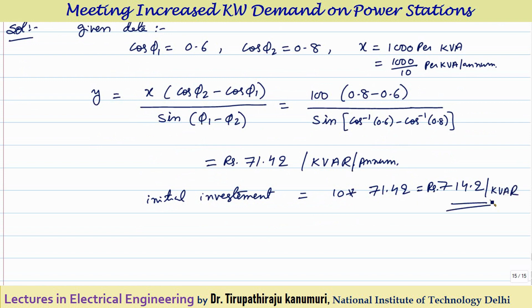So the limiting initial investment is 10 times this, giving 714.2 Rs per kVAR. Up to this cost of power factor improvement equipment, it is economical to go for power factor improvement. If the cost of your power factor improvement equipment is greater than this, it is not economical; if it is less, it is better to go for power factor improvement. This is how we can compare the economics. I hope this concept is completely clear. If you have any queries, leave your comments below and I will answer them. Thank you very much.